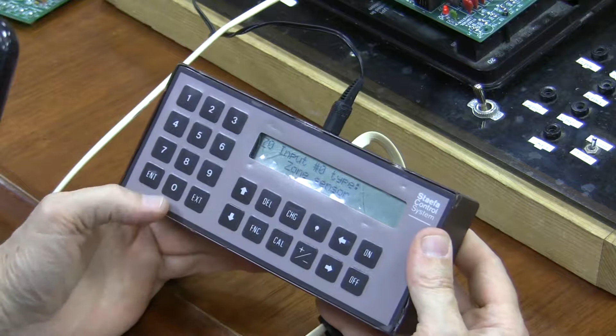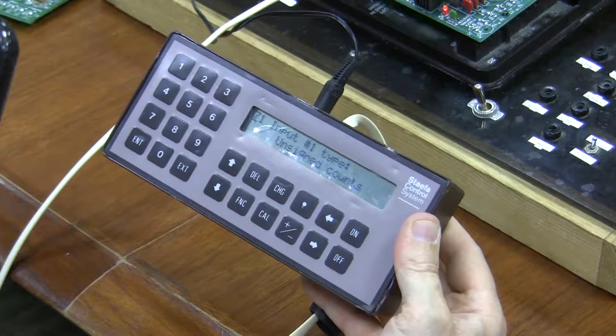Now here I'm on 91, 92, 93, 94. Okay. Now the other thing I can do, so I can scroll by hitting the EXT and coming out to the tens, and I could go back and hit enter on parameter 70, or if I actually know the parameter, I can just type in the parameter. So we knew that zone temperature was 0, 0, so I could hit 0, 0, enter, and see. Now if I wanted to go back to 71, I could go 71, enter. And it takes me right to that parameter. So I'm going to go back to 0, 0, enter, right?